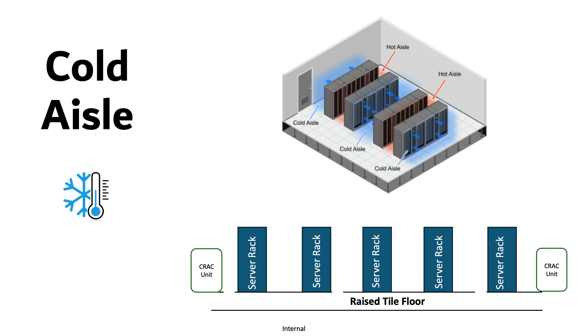If you look from the side view below, here this is the aisle where the front of these servers face each other. Cold air from the air conditioning system is supplied to this aisle, allowing it to be pulled into the front of the servers to cool them down. The cold air is isolated to prevent it from mixing with the hot exhaust air.